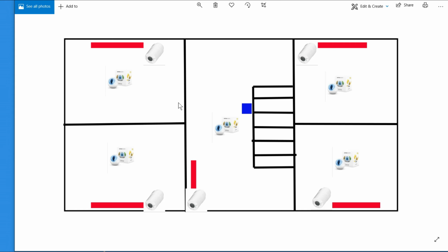But we went even one step further. Because we have motion sensors in every room, we decided to use a bit of occupancy checking as well. So what happens is we've got our set points, the temperature goes below our set point, the signal sends to the boiler and sends to the TRV. So it opens my TRV valve up and fires the boiler up, starts heating, and then this room gets warmed up. The others stay cold. But this room's actually empty, and I don't really need heat in this room. So why would I want to heat an empty room?